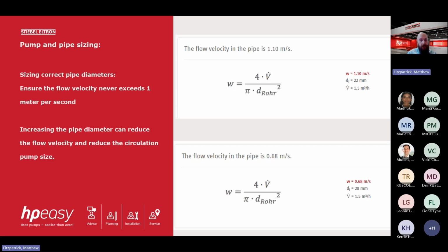So on the first example, we have 22 mil pipes, so flow and returns, and we need to achieve 1.5 meters cubed an hour. So that's our nominal flow rate. Now the flow velocity is 1.10 meters per second. So this will start to create noise inside the pipes to the buffer cylinder and off to the heat emitters and heating circuits. It also changes the way the temperature is delivered.